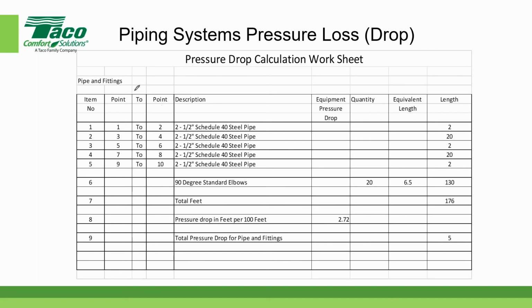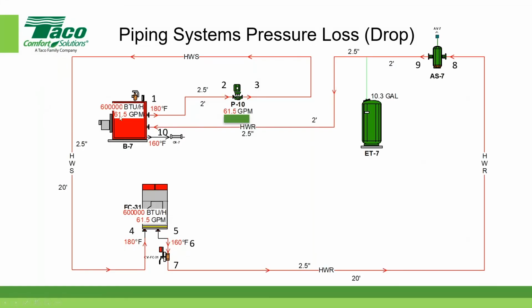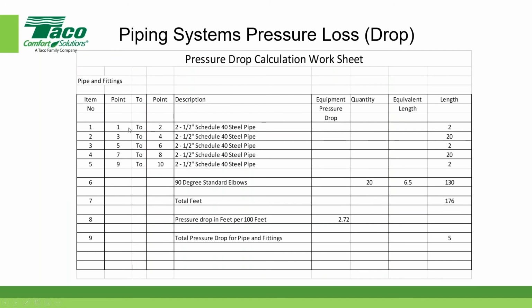So for item number 1, point number 1 to point number 2. Now, if you'll recall from my diagram a moment ago, point number 1 to point number 2 is from the discharge of the boiler to the suction side of the pump. And I'm just accounting for that piece of pipe. So my first process here is to document all the pipe. In this case, that piece of pipe is 2 feet long. So from point 1 to point 2, I have 2.5-inch schedule 40 steel pipe, and the length of pipe is 2 feet. So I can highlight that just so you'll know what's going on.